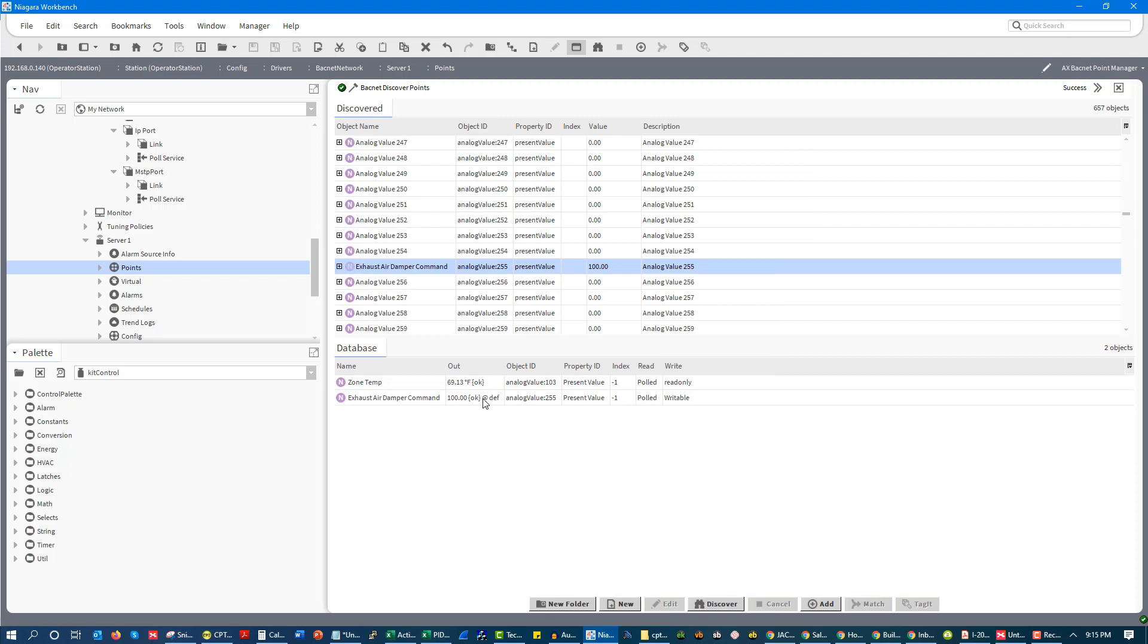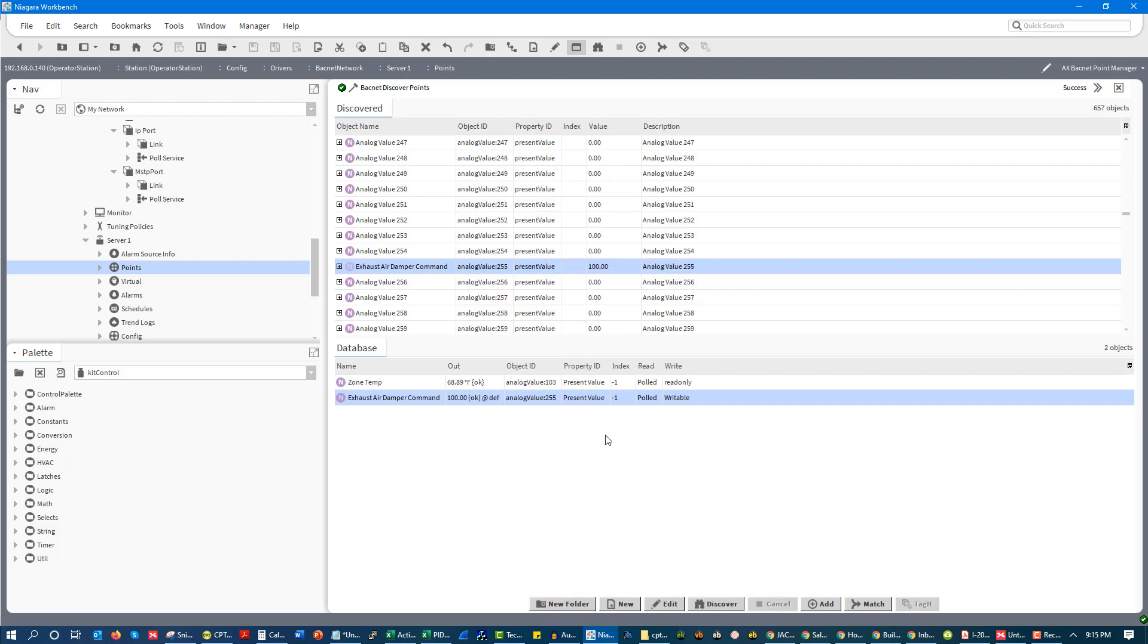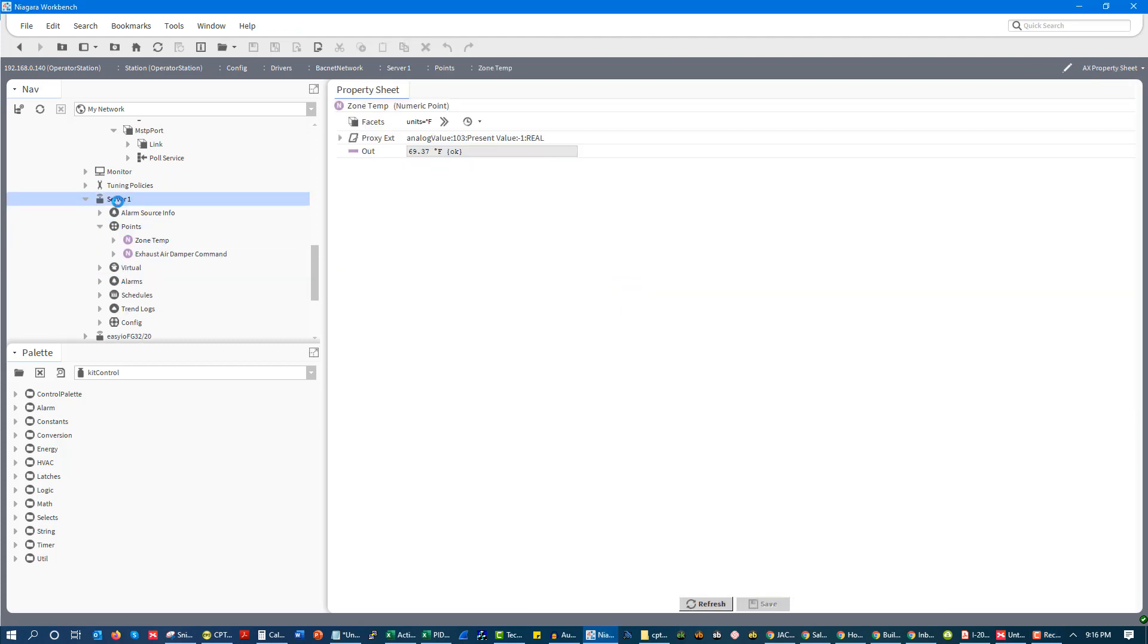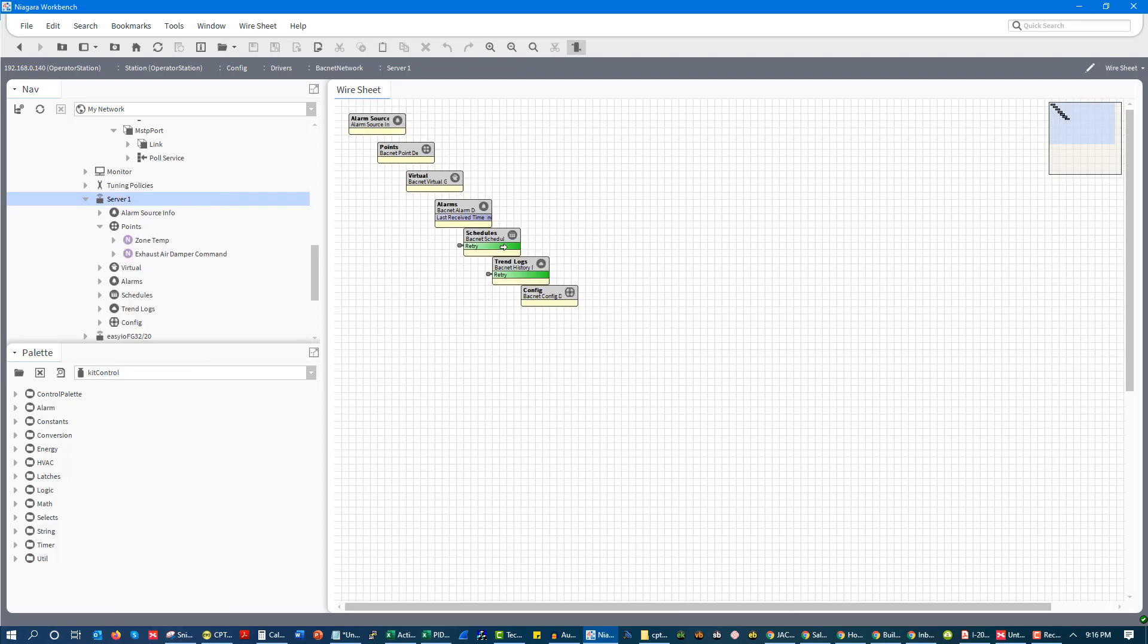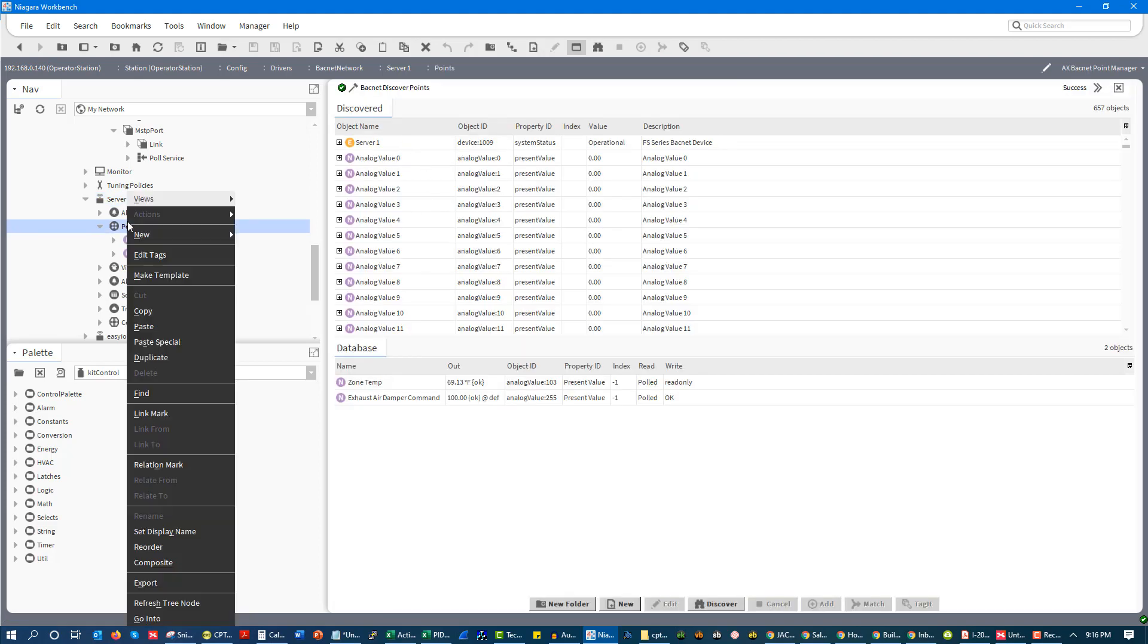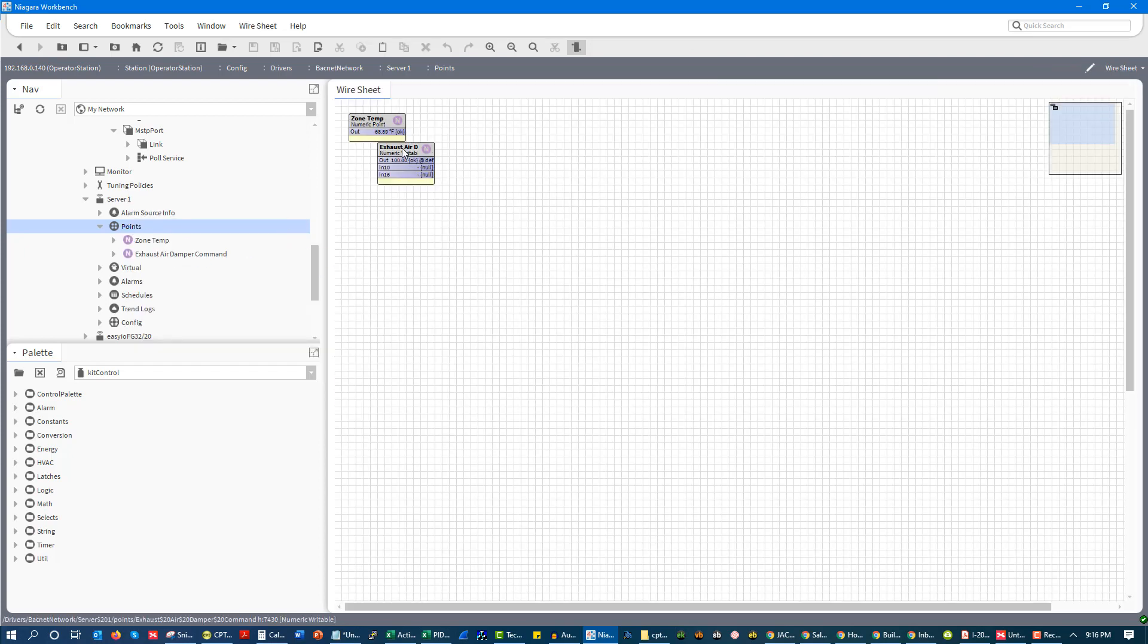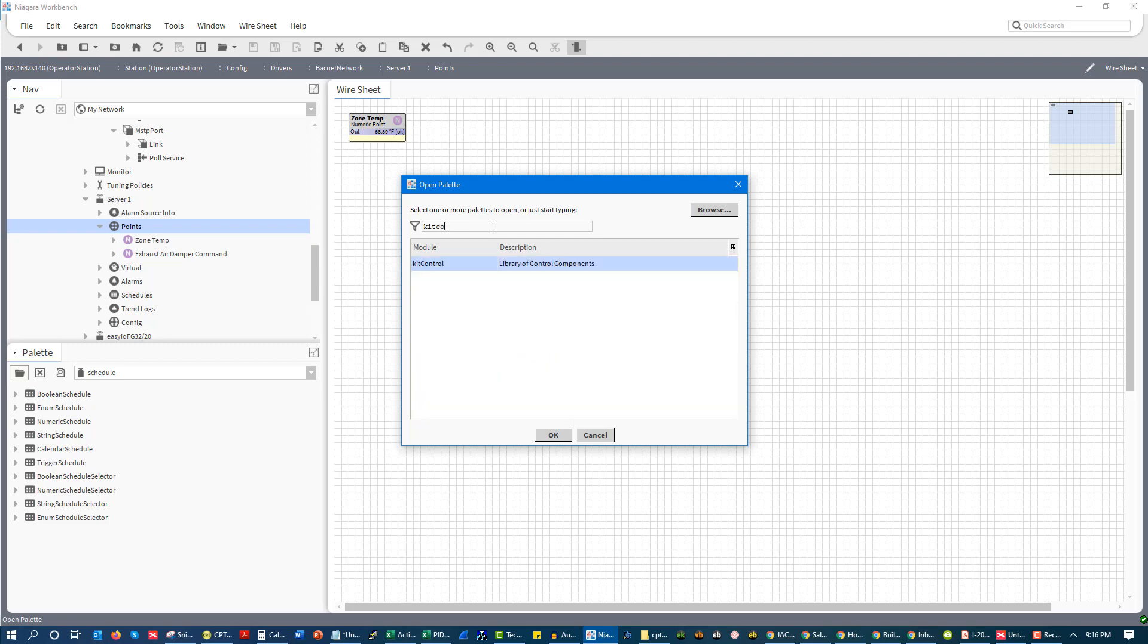And we can see now we have our priority array, because it could say 100 at default. And if we wanted to, we could go and do commands on it. So this is how you go about mapping in points to your building automation system. You go and you discover the devices, and then you discover the points. So if you ever hear someone saying running a device discovery, that's what's going on. You discover the devices via the field trunk, and then you discover the points. And once you've discovered the points and you've added them, they're in here now. So now I can go, and I can go to my wire sheet, and I can see under my points that, actually, let me go to wire sheet view. I can see here, under my points, that the points I have mapped in are right here.